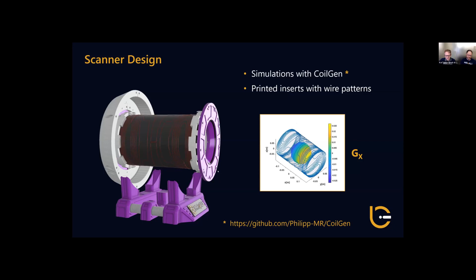Then below the gradient coils, first of all, we have two holders for passive shim magnets. Glued to these holders are a number of shim magnets, indicated in green color here. These are also N40UH magnets, with a little bit smaller size, 3 millimeter. The idea of these shim magnets is a mechanism to correct for inaccuracies that occur during the build of the magnet. The magnet has been built, and then the magnet was mapped using a field mapping approach, and then placements for these shim magnets have been calculated, so that we can compensate and optimize the magnetic field homogeneity. So that's the idea of these two passive shim inserts.